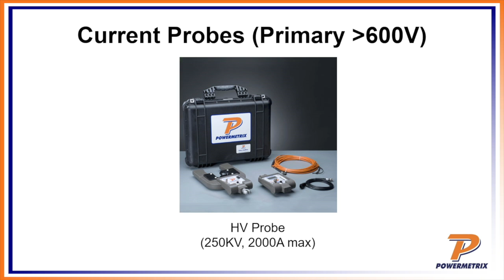Now, with primary, when you get into over 600 volts on the current probe, you're going to need to use the HighVolt Probe for the higher stuff. You can see the rating -- 250 kV phase to ground, 433 phase to phase. So you can get into some pretty serious stuff with this. One of the biggest uses is substations, of course -- everybody uses them there. They mount on the end of an extendo stick to get to the overhead CTs.